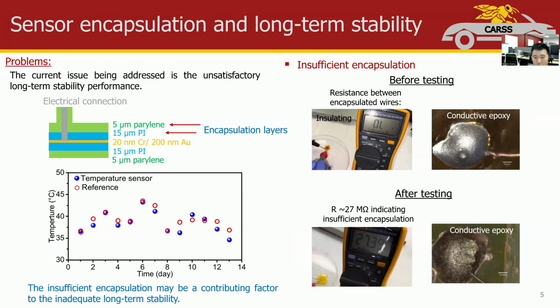The current issue being addressed is the unsatisfactory long-term stability of the temperature sensor. When immersed in PBS, the testing data will be poor over time. Limited long-term stability is likely due to insufficient sensor encapsulation. As we can see here, the color of the conductive epoxy changed significantly, and the protective thin film lost its insulation after long period test. This observation suggests that the encapsulation fails to protect the sensor effectively from water moisture.